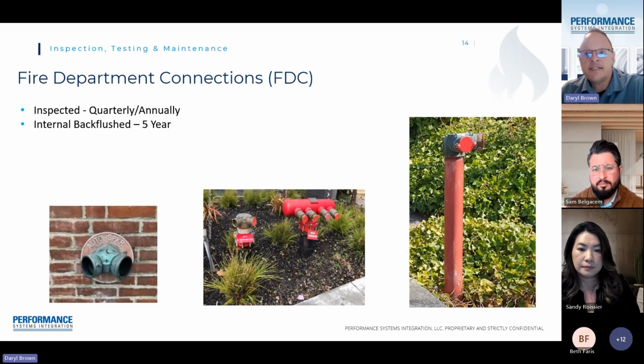Next, you have what we call FDCs, or fire department connections. If you see these outside your building, you have fire sprinklers in your building. These are mainly here because the city supplies water to your sprinkler system. If for any reason city water pressure goes down, the fire department can pull up their fire trucks, hook up their water truck, and manually pump water into the sprinkler system, thereby activating the system and flowing water in through the sprinkler head. These are other major components. This is visually inspected every quarter, tested annually, and this one actually has some extra requirements, a 5-year certification backflush, and we'll go over that a little bit later.